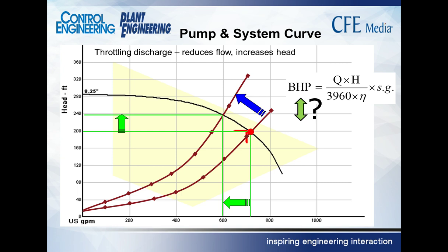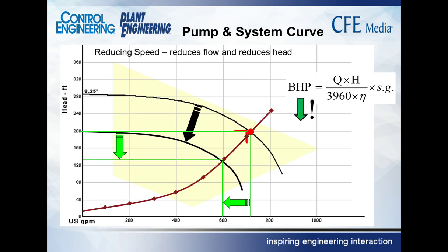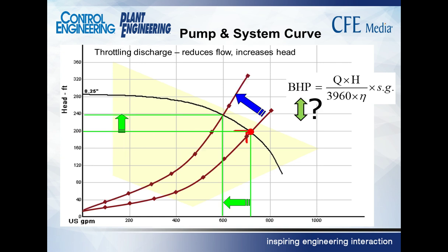So the other opportunity, if you recall, we said there's two ways to reduce the flow. You could either throttle the throttle valve, close the throttle valve and throttle the discharge, or we could lower the speed of the pump. If we lower the speed of the pump, we move the pump curve down along the system curve. When we throttle the pump, we move the system curve up the pump curve. That's throttling.